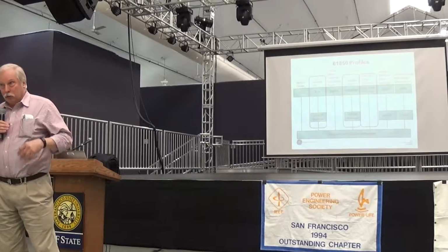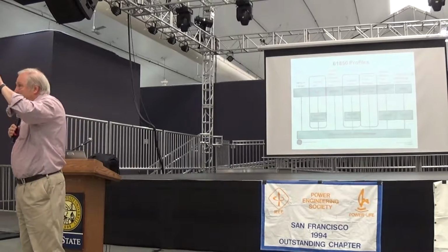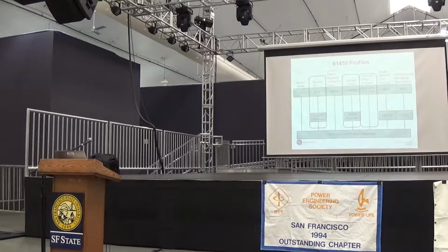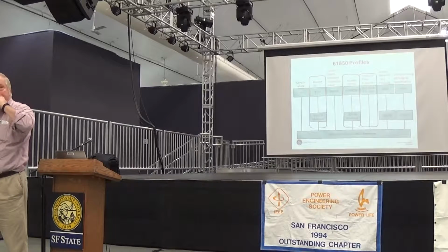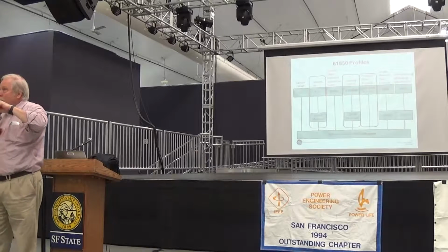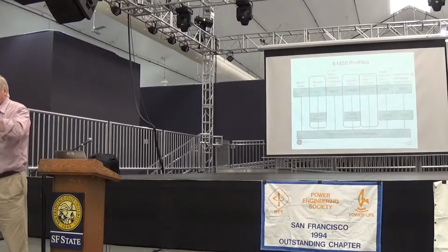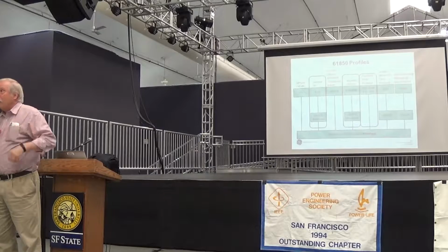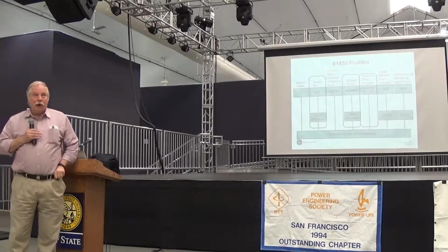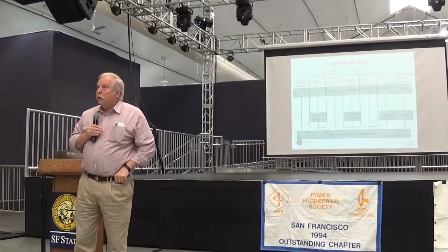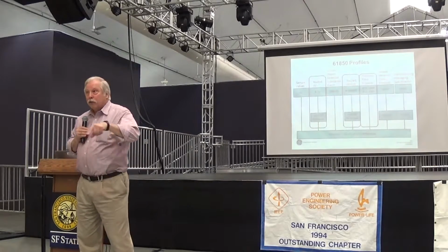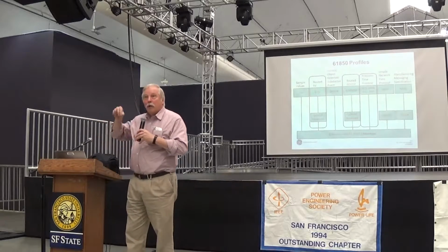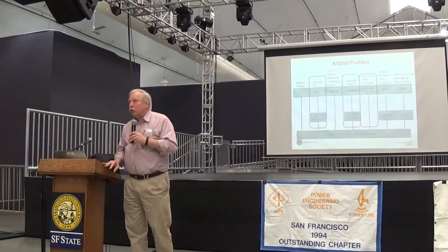So in a substation, we need this today in 2 different applications. The first application is for sample values. This would have been the process bus material that Steve talked about. The second application is when we compute synchrophasors. Both of those applications need precision time. So there is now a profile that's part of 61850 that defines how to implement precision time. Later on, assuming I have enough time here, I will talk about how this precision time protocol works.